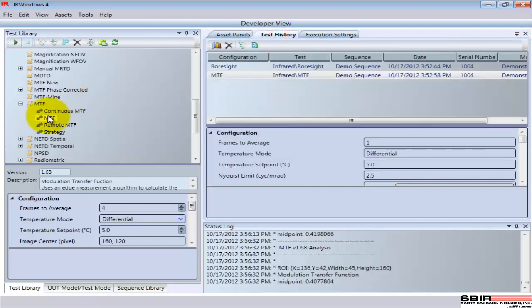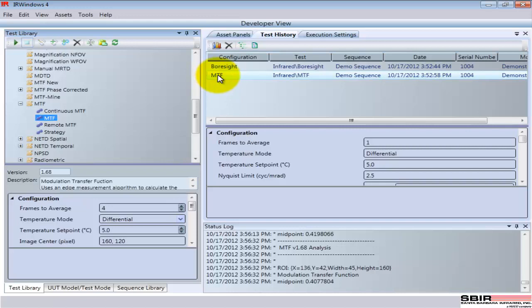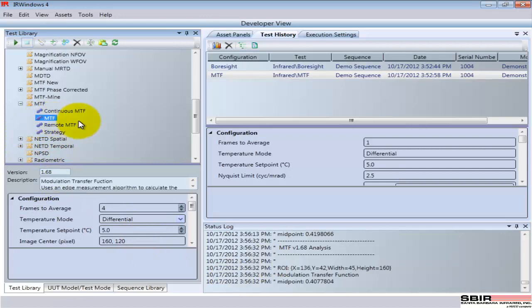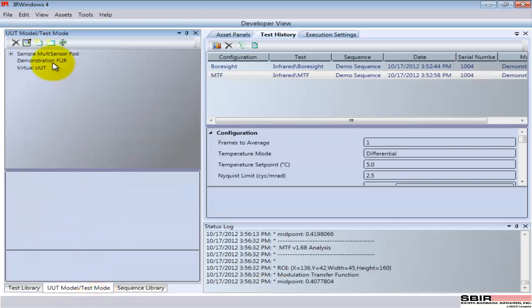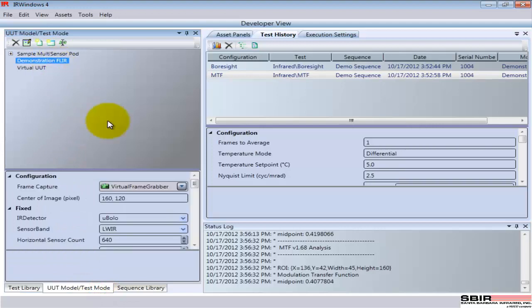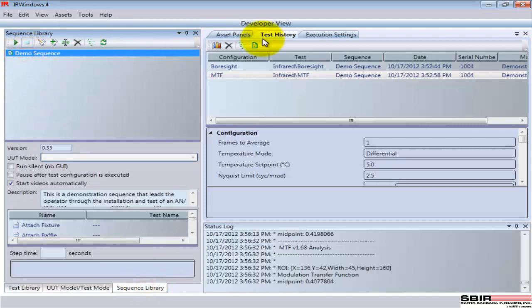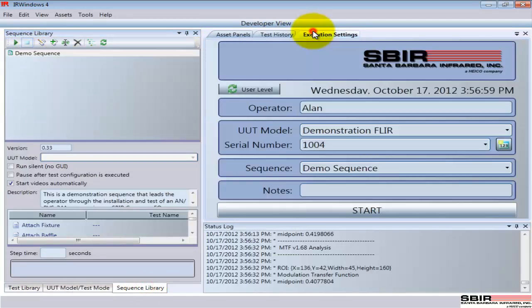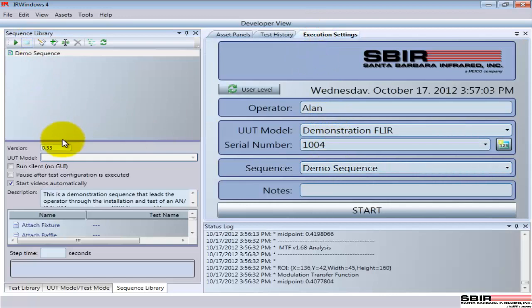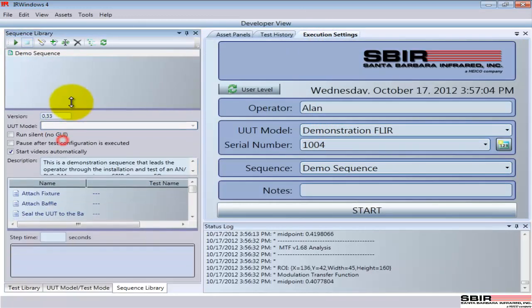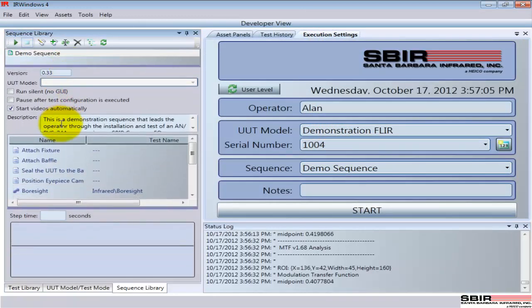So that's the test, individual test and test configurations. Other things I set up are the information about the device that's being run. So here's the demonstration FLIR and some of the information about the camera. Also the sequence library. Here's that demo sequence as the one that we ran earlier, and here are the details of the steps involved with that sequence.